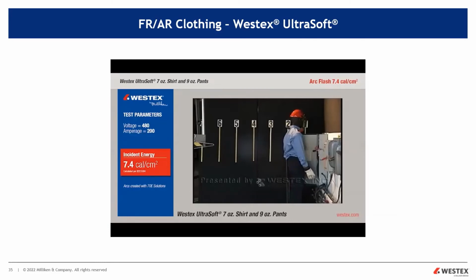However, the level of risk of arc flash burn injury is higher for task-based programs because employees who are working around the energized hazards are expected to recognize that and put on the appropriate PPE. You're relying on your employees doing exactly what they're supposed to do 100% of the time. So whenever you have a human variable, it's subject to these error precursors such as rushing, fatigue, complacency. It's always going to increase the level of your risk if you have these error precursors. So regarding reducing the risk to as low as reasonably practicable, or ALARP, involves weighing the risk against the trouble, time, and money needed to control it.